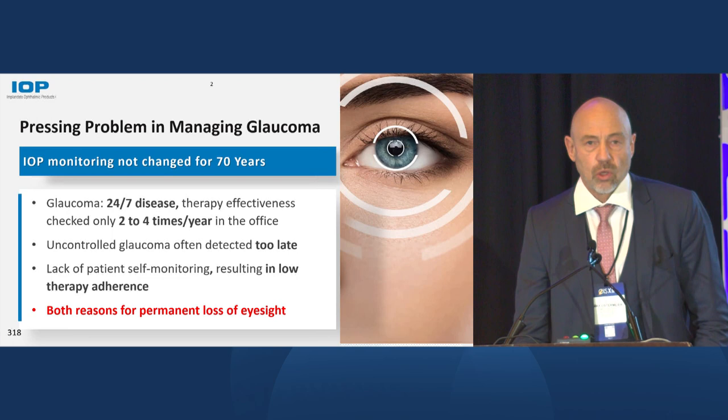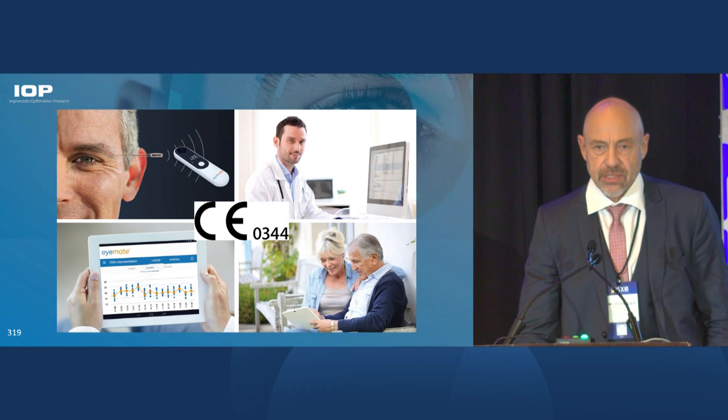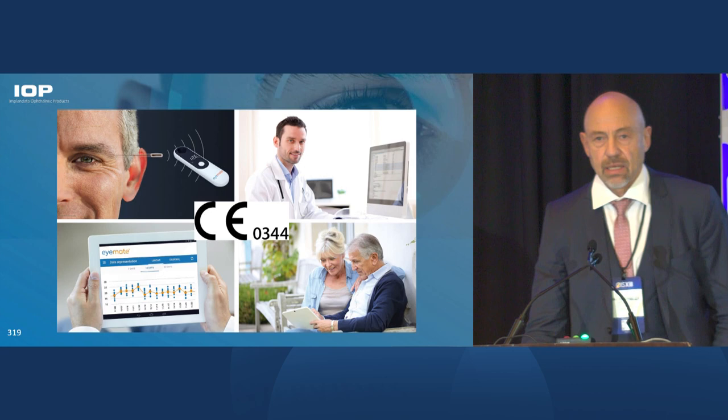To overcome this problem, we have established the eyemate system, which consists of a tiny implantable microsensor placed permanently in a patient's eye. Today it's done either in combination with cataract surgery or in combination with glaucoma surgery. That device is powered externally by RFID. For that purpose, we have a handheld device by which the patient initiates the measurement. In the next step, we are also integrating the RFID electronics into a nighttime device, so that data can be fully automatically collected without any patient interaction.